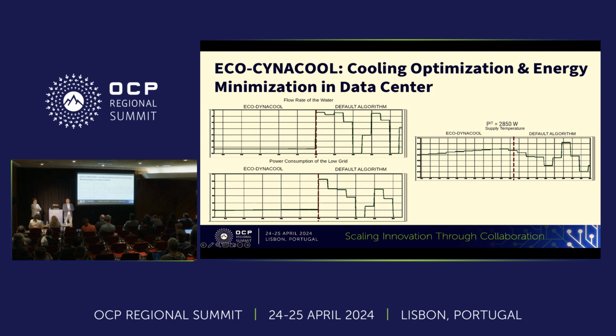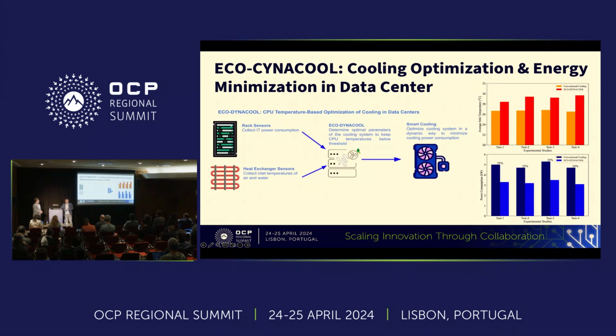Our algorithm can predict the CPU temperatures in an accurate way, so the cooling parameters can be optimized depending on these values. Then we compared the power consumption of the cooling system with the current cooling system in the EMPA data center, and we have seen that EcoDynaCool can reduce cooling power consumption by up to 35% compared to the conventional or current cooling system.